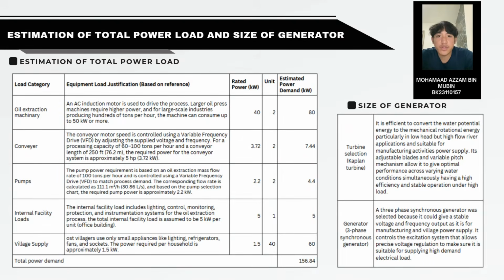For the estimation of total power loads, the total power demand is 156.84 kilowatts. This includes the heavy oil extraction machine, conveyor, pumps, internal facility loads, and also the power requirement for the 40 village households. For the size of the generator, we have selected a Kaplan turbine. It was chosen because its adjustable blades allow for optimal performance in low head, high flow river conditions typical for this type of application.